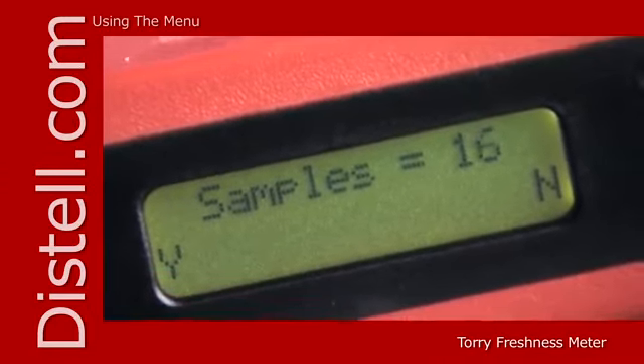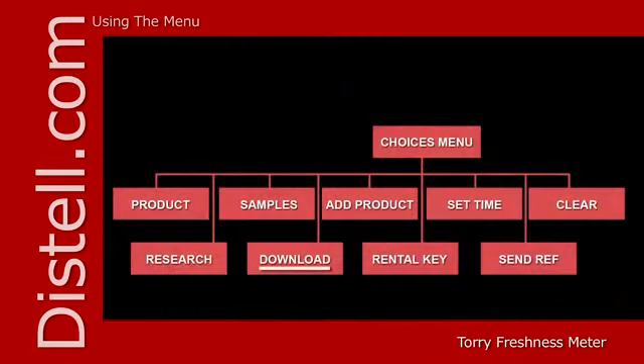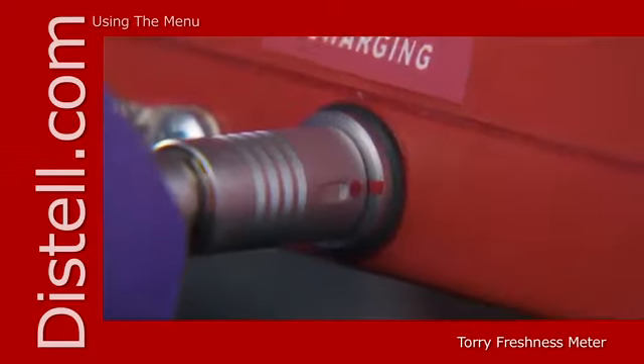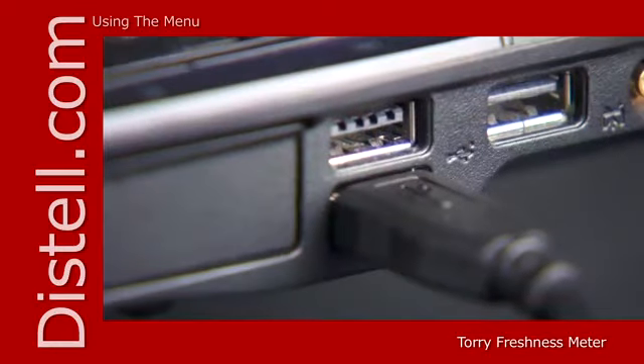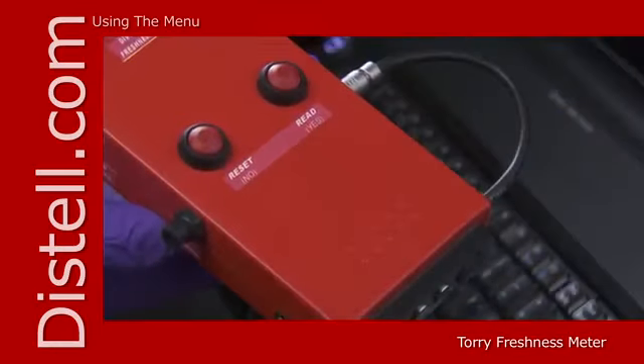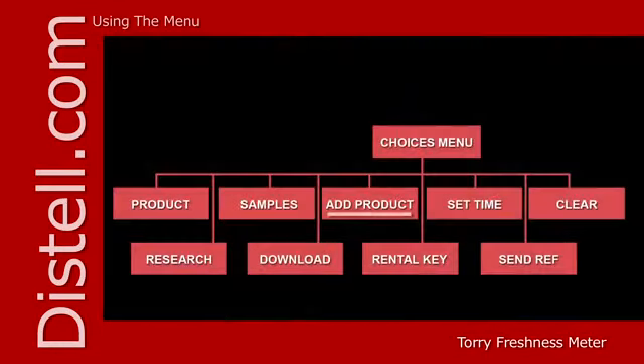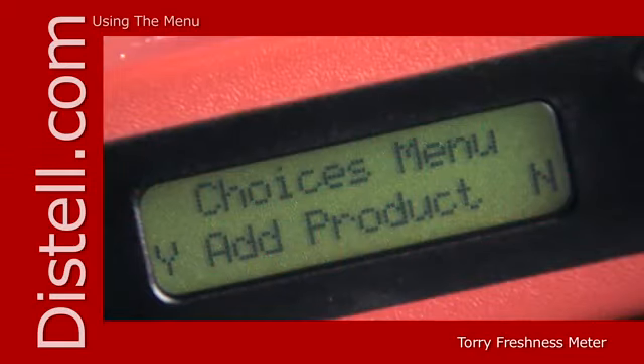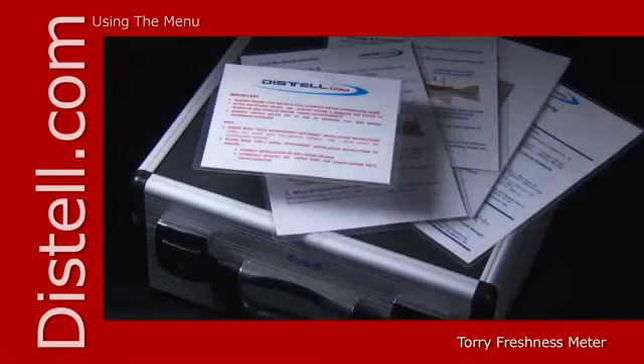The Download function allows the download of data from the meter to a PC. After download, you will be given the choice to erase the data on the meter. See Download section for explanation. The Add Product function allows you to create custom calibration or install a revised calibration received from Distell. See the user manual for details.